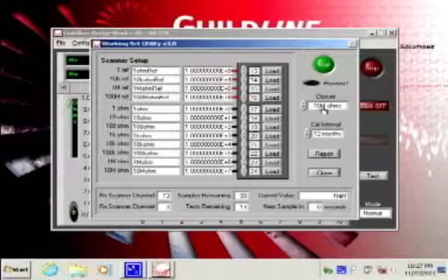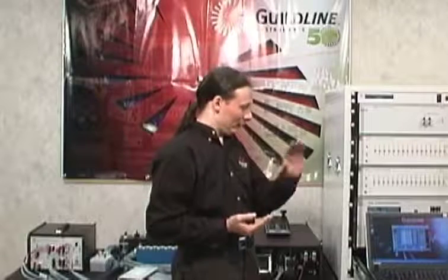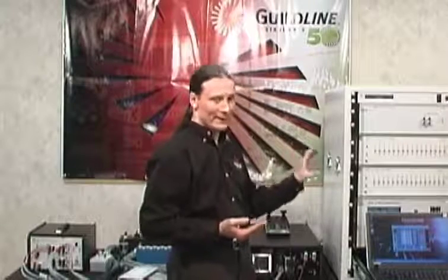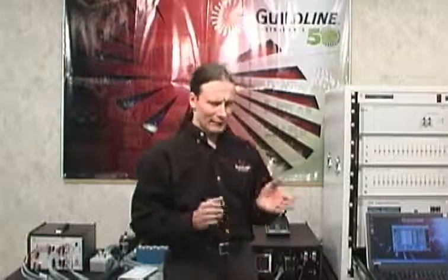And again, a good practice is using the preview option inside this window, which shortens all the tests down to about 10 samples and runs the bridge at an accelerated reversal rate, just to keep the system running really fast, but to make sure that the thing can actually make the measurements and that there's no problems with your wirings and that sort of thing. And it's a good practice. Takes maybe half an hour to an hour.